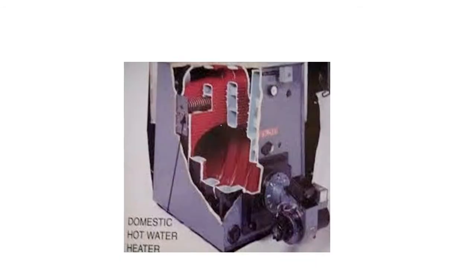Tankless coils use the heat from a boiler to transfer heat to the domestic water. The coil is actually bolted into the boiler, but it's an entirely separate system. The coil itself is basically a long run of copper tubing with fins cut into the outside of it. The inlet and outlet of the coil are only a few inches apart from one another, but there's quite a bit of pipe in between. By the time the cold water gets through all the pipe, it comes out very hot on the other side.